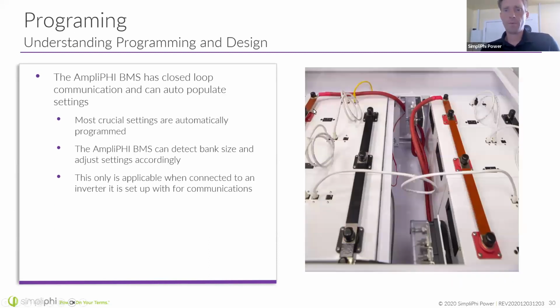So I want to point out a couple of things about the install here. Here we're showing the use of bus bars. Bus bars are a great way to connect batteries up. I had somebody call in yesterday asking why we don't recommend connecting with cables. The reason is that the bus bars that we offer have a much larger cross-sectional area for current to flow through, and that minimizes any difference in voltage that the individual batteries see.